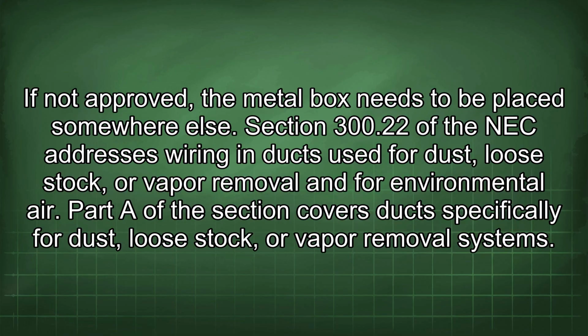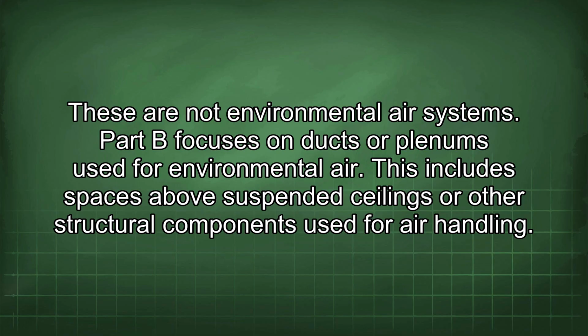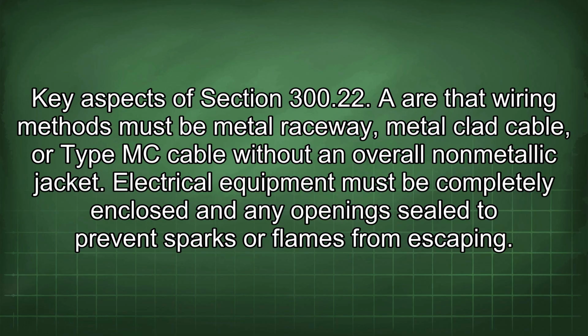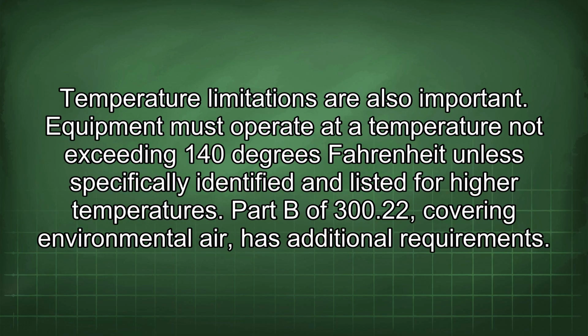Section 300.22 of the NEC addresses wiring in ducts used for dust, loose stock, or vapor removal and for environmental air. Part A covers ducts specifically for dust, loose stock, or vapor removal systems. These are not environmental air systems. Part B focuses on ducts or plenums used for environmental air. This includes spaces above suspended ceilings or other structural components used for air handling. Key aspects of Section 300.22 are that wiring methods must be metal raceway, metal-clad cable, or Type MC cable without an overall non-metallic jacket. Electrical equipment must be completely enclosed and any openings sealed to prevent sparks or flames from escaping. Temperature limitations are also important. Equipment must operate at a temperature not exceeding 140 degrees Fahrenheit unless specifically identified and listed for higher temperatures.